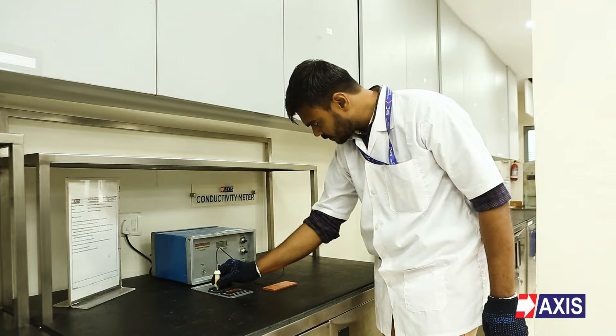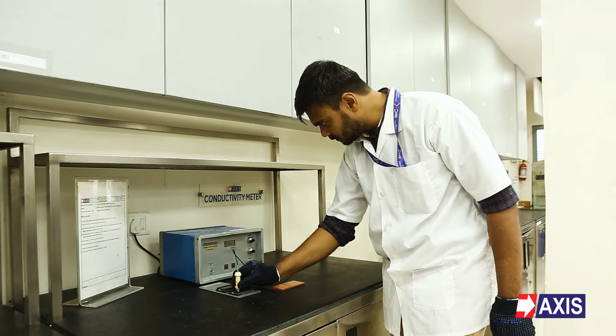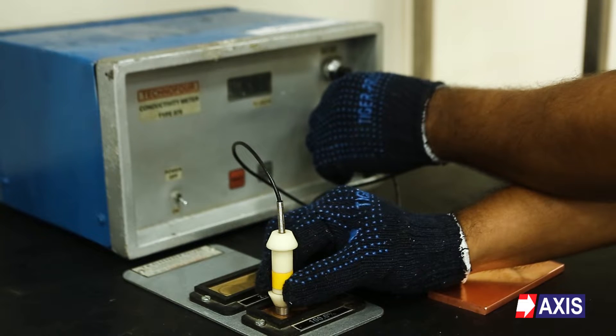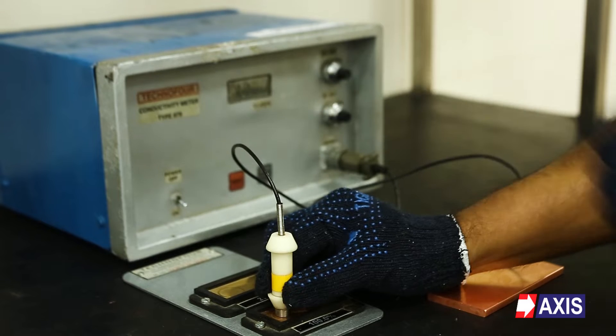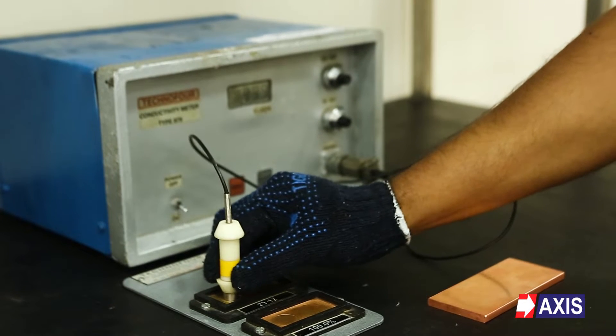Procedure. First, the machine probe needs to be calibrated in line with the values mentioned on the master plate. After calibration is done with the master plate, keep the probe on the test piece, example, copper lug, copper busbar or any other product, to measure the electrical conductivity.